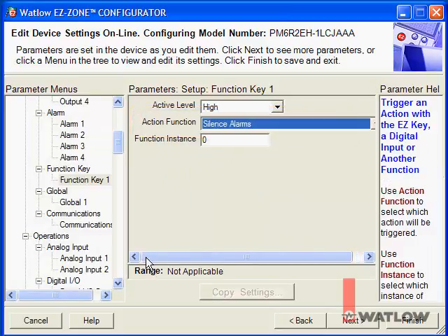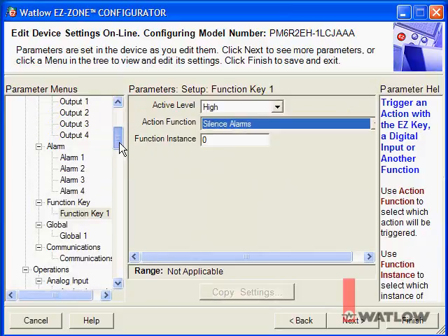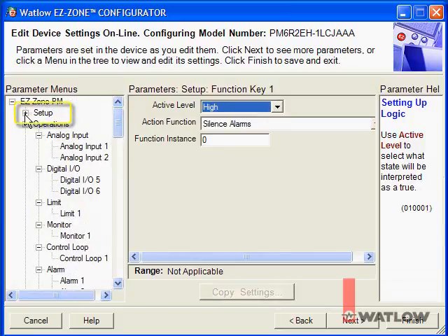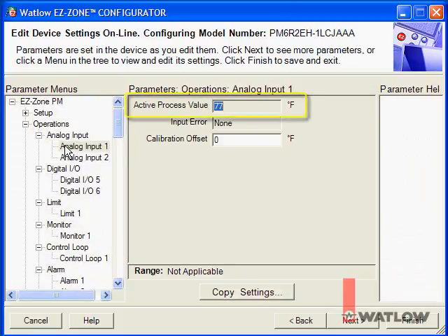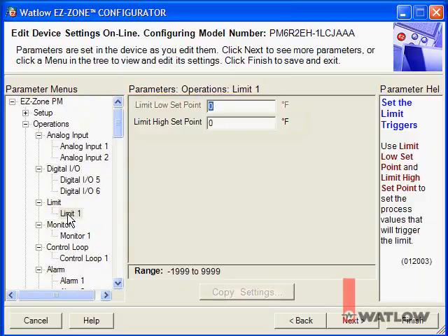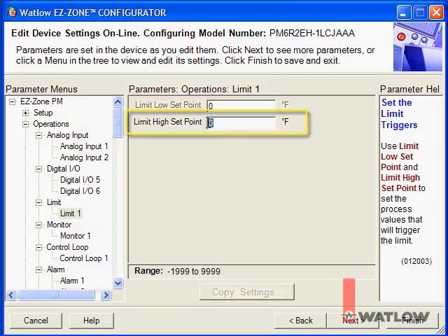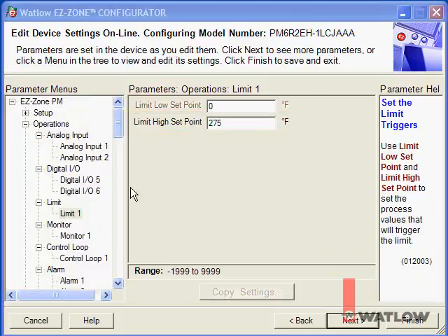That's all we need to do on the setup page. Now let's set the initial operating settings. Click the minus sign next to the setup page to hide the setup menus and bring the operations menus into view. On the operations page Analog Input 1 menu, you can see the temperature measured by the first thermocouple. Keep in mind that EZ-ZONE Configurator is for controller configuration and is not HMI or SCADA software — these values update every 5 seconds or so. On the Limit 1 menu, I'll set the Limit High setpoint to 275; above that, the limit will shut off the power to the heater.